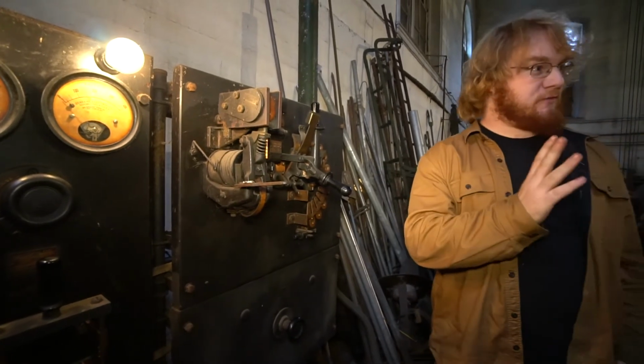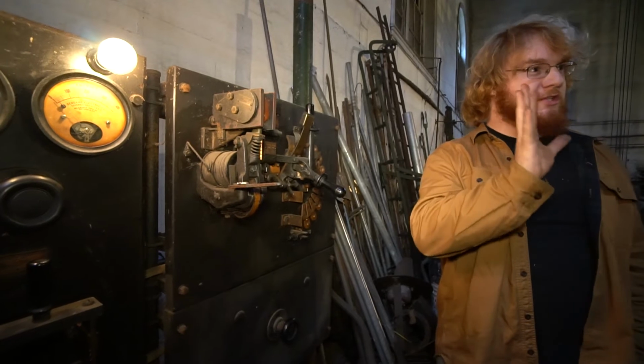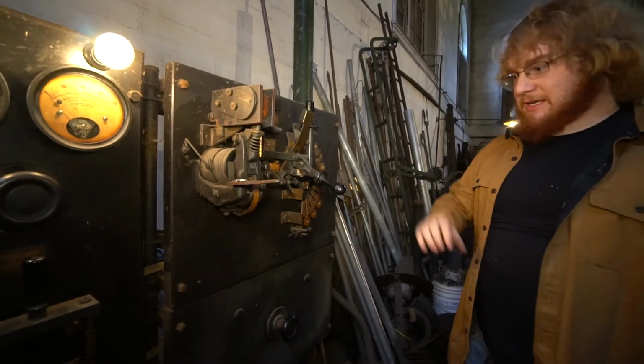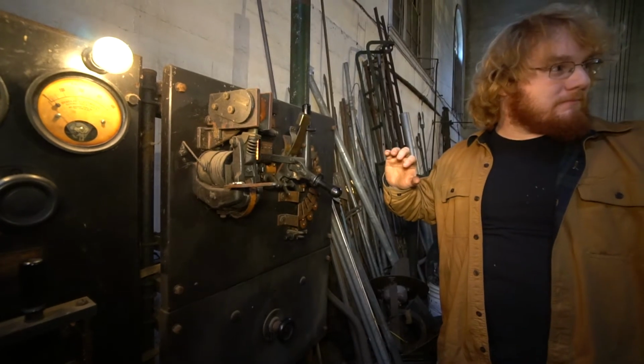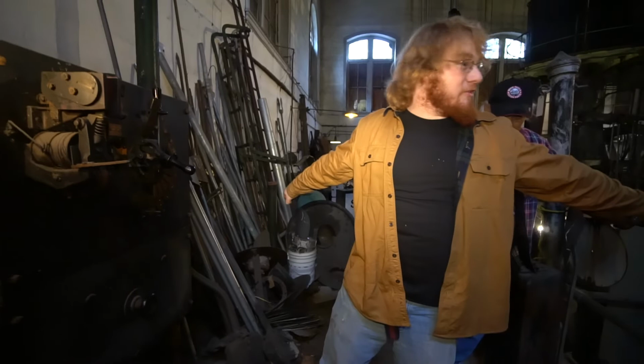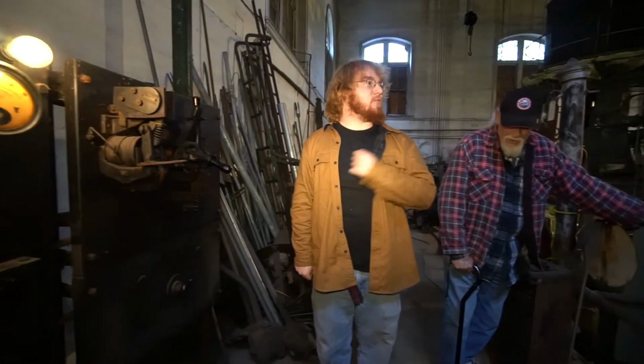Now, a word of advice, if you're running an old panel like this, you only touch it with one hand, and your other hand should really be behind your back. Because let's say I touch this and something else, and I'm potentially now part of a circuit, especially if I'm leaking all the way across and I'm on ground, then I'm screwed. I've got 200 volts across me.